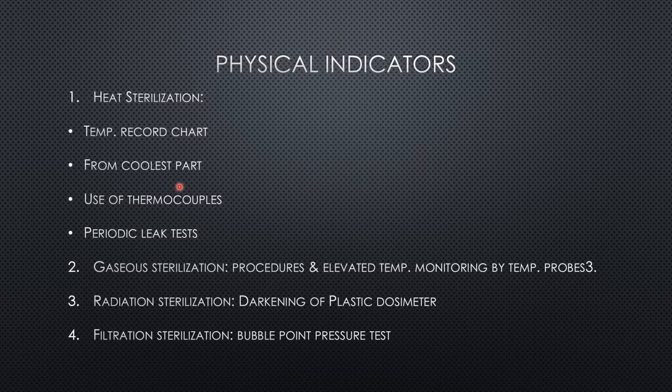Heat distribution and penetration within a sterilizer can be assessed by use of thermocouples placed at selected sites in the chamber. Autoclaving depends upon steam under pressure as well as temperature, so pressure measurement is an essential part of the physical monitoring of the process. In addition, periodic leak tests are performed in pre-vacuum steam sterilizers to assess the efficiency of air removal before the introduction of steam.